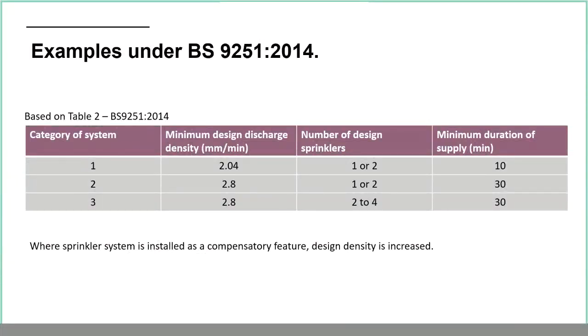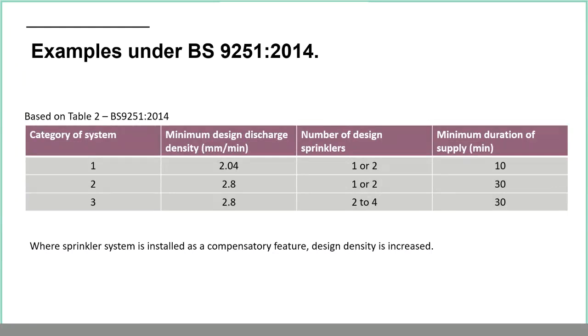Once you've decided the category, you apply it to table two, which gives the minimum discharge density and the number of design sprinklers — the number of heads allowed to operate simultaneously. Under 9251 that's a maximum of four heads. Statistics show the vast majority of cases are controlled by one head, occasionally two; three or four is very rare. The table also gives the minimum duration.